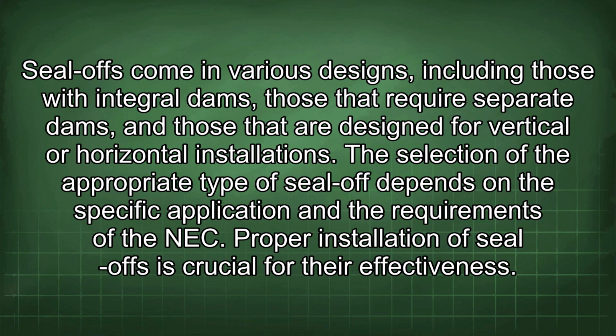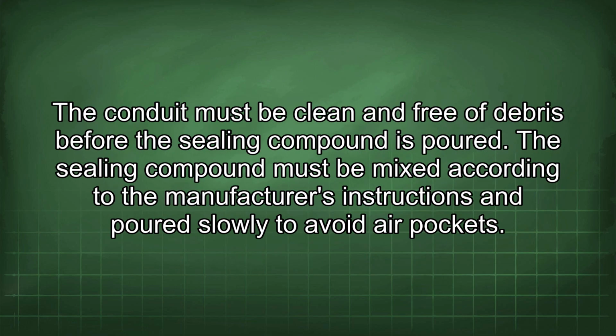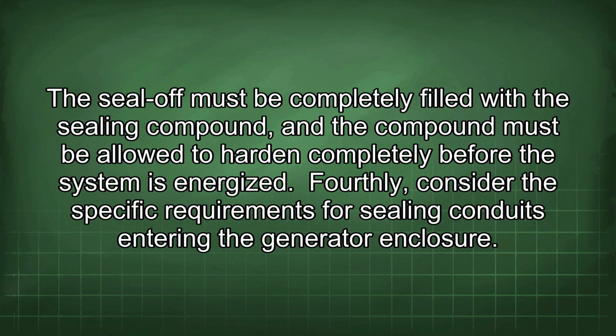The selection of the appropriate type of seal-off depends on the specific application and the requirements of the NEC. Proper installation of seal-offs is crucial for their effectiveness. The conduit must be clean and free of debris before the sealing compound is poured. The sealing compound must be mixed according to the manufacturer's instructions and poured slowly to avoid air pockets. The seal-off must be completely filled with the sealing compound, and the compound must be allowed to harden completely before the system is energized. Fourthly, consider the specific requirements for sealing conduits entering the generator enclosure.